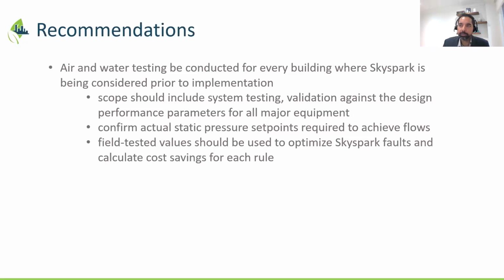One of the challenges we noticed during the implementation phase was the lack of air testing and water testing results on the buildings, which hindered some of the fault implementations, where we didn't know what should be an actual high performance value for a static pressure set point, or for a differential pressure set point for pump systems. So one of the recommendations that came out of that was to ensure, if you want the best use of fault detection, you do that air and water testing ahead of time, so you get values that can be used as set points to calibrate to the high performance building.